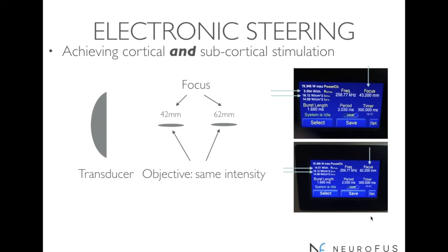So if you were to change the focus depth, as shown in the top right corner of each example, from 43.2 millimeters to 62.2 millimeters, it will automatically change the acoustic power—indicated by P actual on the touchscreen—to achieve the same ISPPA.